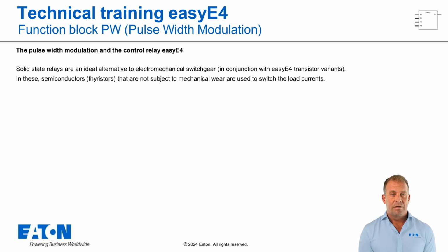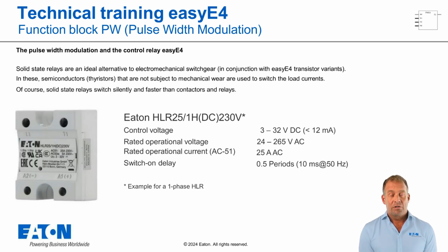Solid-state relays, in conjunction with easyE4 transistor variants, are an alternative to electromechanical switchgear. Semiconductors, thyristors, are used to switch the load currents, which are not subject to mechanical wear. Of course, solid-state relays switch silently and faster than contactors and relays. With the solid-state relay shown, the current flow begins after only 10 milliseconds. In this case, the minimum duty cycle can be reduced and the period duration shortened.